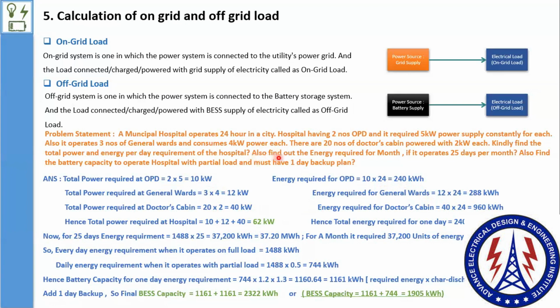Now, what they asked next: find out the energy required for a month if it operates 25 days per month. So for a month we need to do the calculation. Since it operates only 25 days, the 25 days energy requirement would be 1488 into 25 directly. We get 37,200 kilowatt hour, which we can also show as 37.20 megawatt hour. So for a month it requires 37,200 units of energy to operate the hospital.